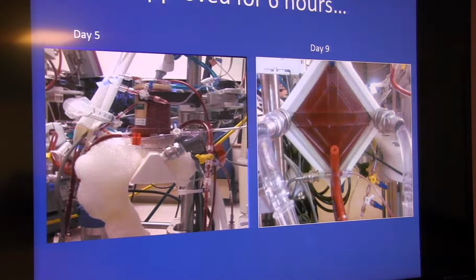So the old oxygenators, we would see that a lot, or you would just walk in and realize they're changing the diaper on the oxygenator so much that you're losing huge volume from your patient, and so then we would change those oxygenators. This is why I think people forget what the pre and post gases are really for, because the majority of the time when you hear those numbers, they're not going to be that different day to day. In our little neonates that we're running at, say, flows of 300 or 400 milliliters per minute, it is not uncommon that their sweep speed is down around 0.1 liters per minute, and even with that, their PaCO2 is lower than you want it to be. It'll be 0.1, 0.1, 0.1 for days on end, and then maybe it'll be 0.2, and the FiO2 will be 55 or 60%, and it just kind of rides that way.